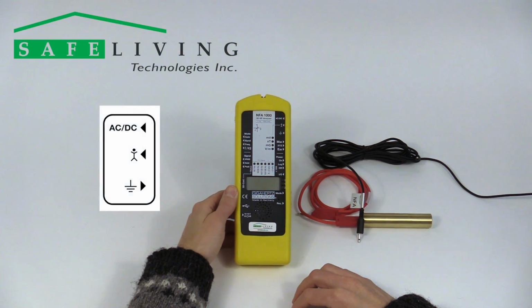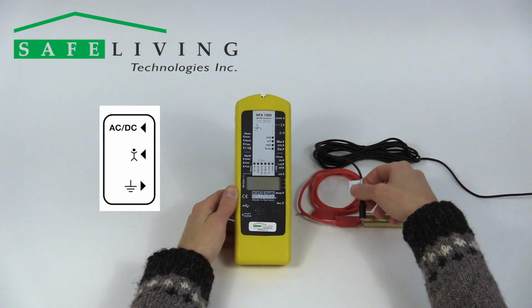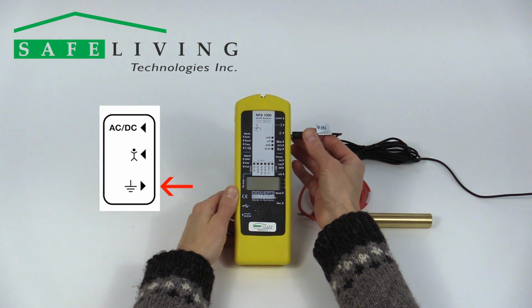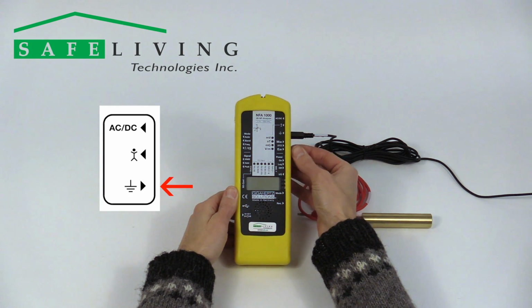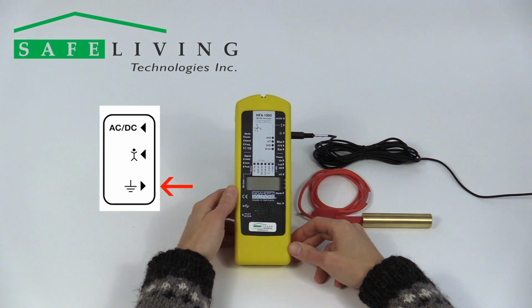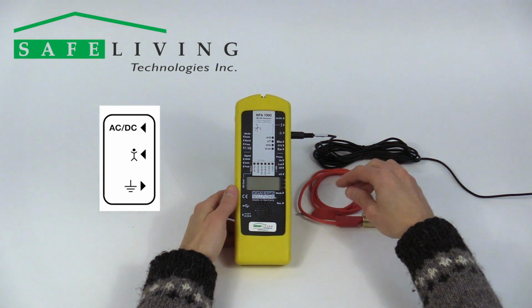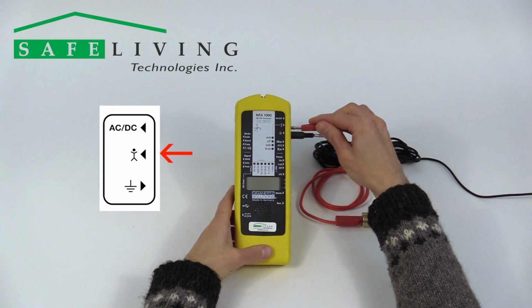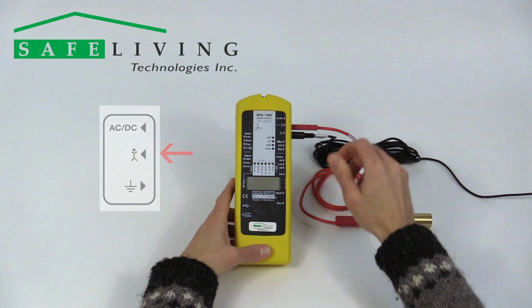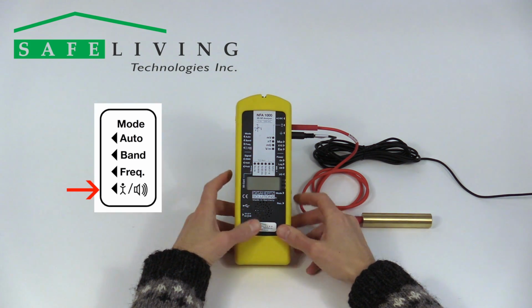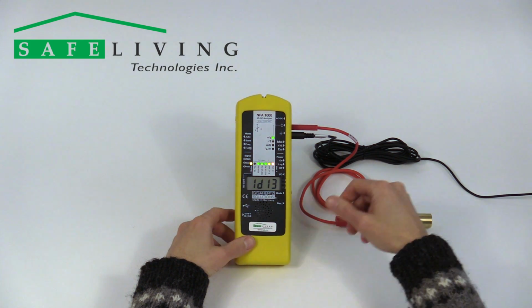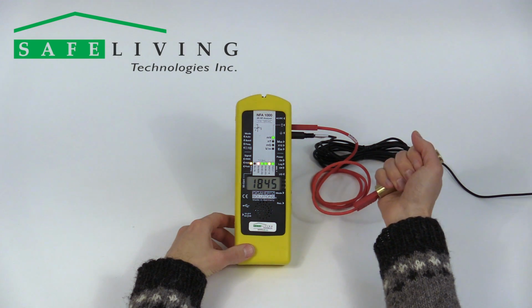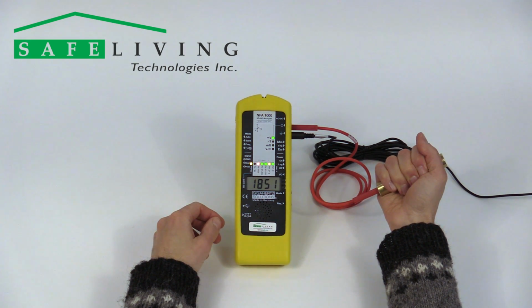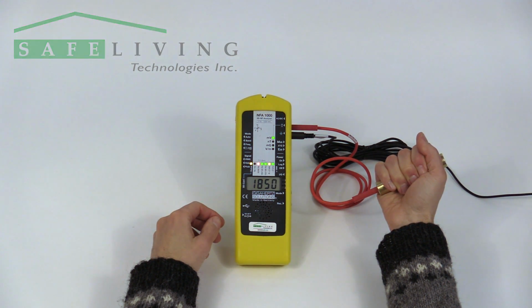To measure body voltage, connect the meter using the included 17-foot cable to a ground source such as a water pipe or to an electrical outlet using a grounding plug. More information about grounding techniques is included in our advanced electric field measurement video. Connect the hand probe to the body voltage jack as shown. Switch the mode to body voltage and power the unit on. Firmly hold the hand probe as shown and simply read the measured value in millivolts. For the most accurate measurements, your hand should be somewhat moist.